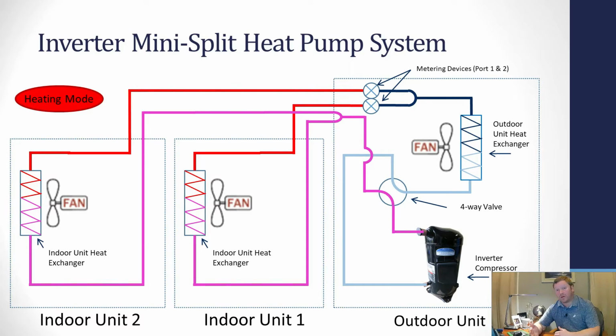If I only have 2 indoor units, a lot of the time, honestly, you can be just fine. The goal when you have multiple indoor units is to set them for whatever temperature is comfortable and then leave them there. The last thing that you want is to turn an indoor unit on and create a large delta between your target temperature and return air temperature, which forces that compressor to ramp up. Because then when it ramps up to recover that one zone, all the other zones are going to get all that hot gas as well.